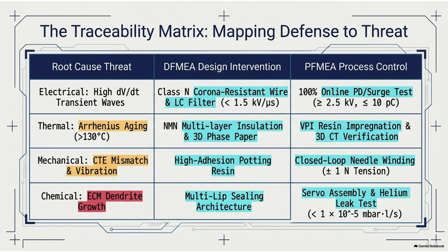Through the extremes of pressure. First, they place the entire motor assembly into a sealed chamber and pull a near vacuum. Like space vacuum. Almost. They drop the ambient pressure down to less than 10 millibars. This physically sucks every microscopic pocket of trapped air out from between the thousands of individual wires. And then, while it is still in a vacuum, they introduce the liquid resin. Right. But they don't just let it settle. They hit the chamber with extreme high pressure, greater than 6 bar. Wow. They violently force the liquid resin deep into every single microscopic crevice where the air used to be, ensuring a completely solid, void-free matrix.